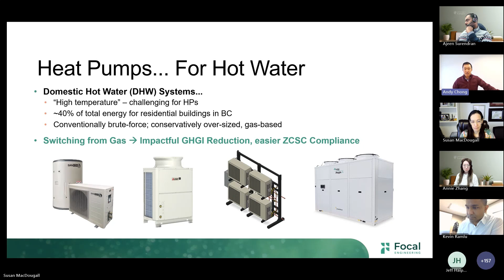I just want to re-emphasize that zero carbon step code compliance does not mean an outright ban on natural gas. I still think natural gas has a very important role in most buildings for peaking and backup. I wish we had time to show some fancy graphs on how to right-size heat pumps and how much we oversize these systems when designing for the coldest day. But I'll say: design for 3 degrees warmer than the coldest day, and throw a boiler at the rest of it, because you'll just sip gas for a small fraction of the year, and you get the benefit of a right-sized heat pump working at its prime capacity, without oversizing the system and without paying through the nose for something sitting in standby 97% of the year.